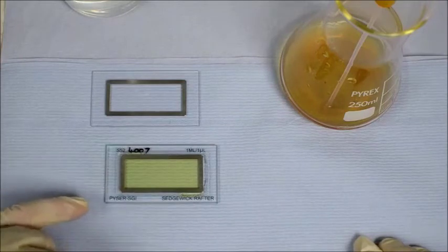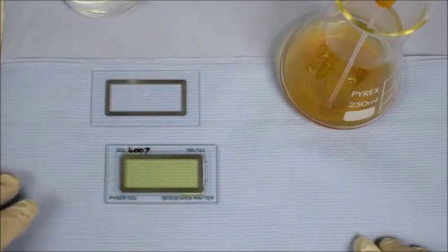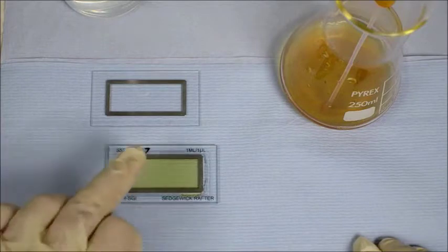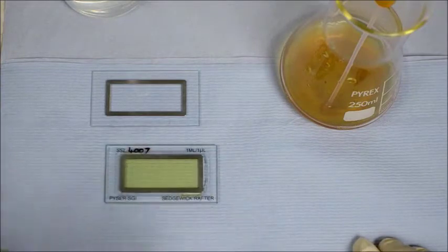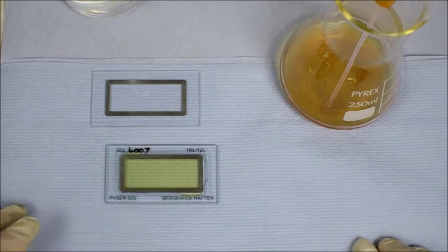Now, the gridded version, on the other hand, there is no need for a reticule at all here. The square pattern on the floor of the chamber becomes the guide. It's ideal for use with a stereo zoom microscope without the need to carefully set up the precise zoom or magnification before counting the sample.